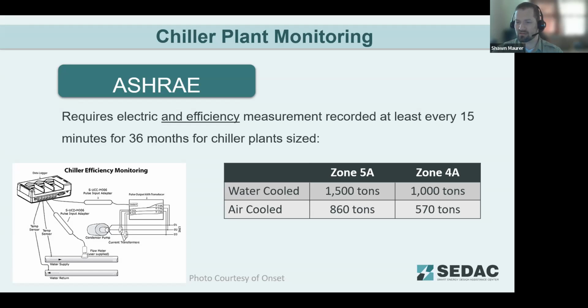Some of this may already be available from onboard controls for new chillers, but the importance is understanding the accessibility of that data, putting it in a central place where operators can see it, make use of that data, and it's not something that just is there and never gets looked at. For campuses and other large facilities that have multiple chillers, understanding which chillers are more efficient at different situations can help optimize those plant processes. So that's the goal of this chiller plant monitoring in ASHRAE.